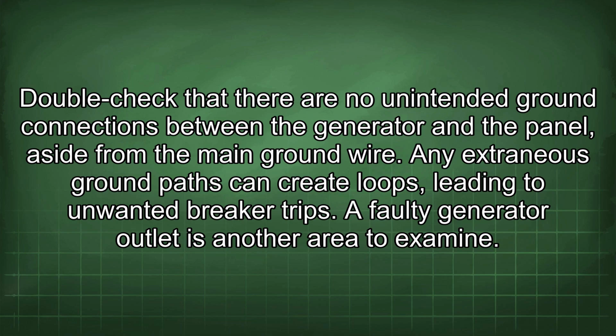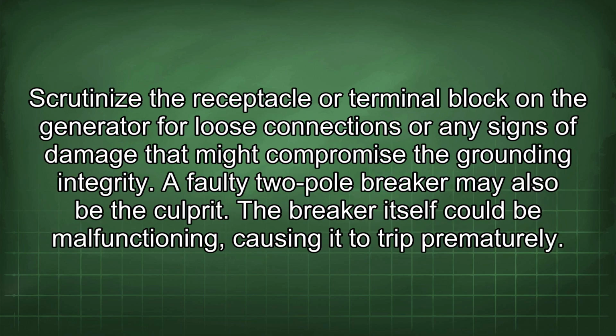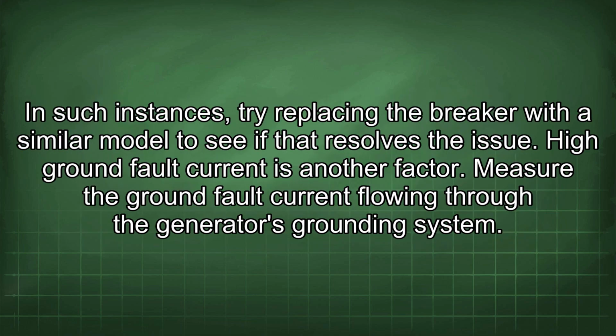A faulty generator outlet is another area to examine. Scrutinize the receptacle or terminal block on the generator for loose connections or any signs of damage that might compromise the grounding integrity. A faulty two-pole breaker may also be the culprit. The breaker itself could be malfunctioning, causing it to trip prematurely. In such instances, try replacing the breaker with a similar model to see if that resolves the issue.